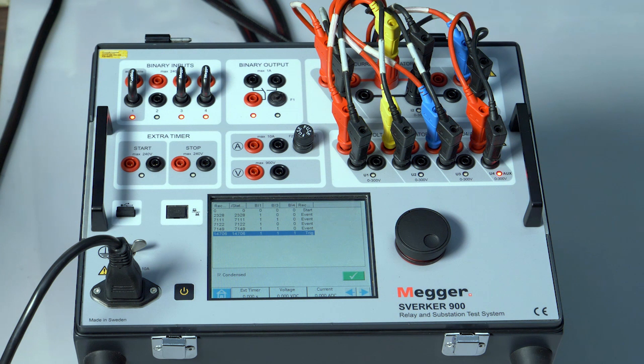Binary input 1, 2, and 3 are configured for ampersand logic. When we perform this test in state sequencer, the state will be stopped when all the three poles of the breaker are open, thus confirming a three pole trip.